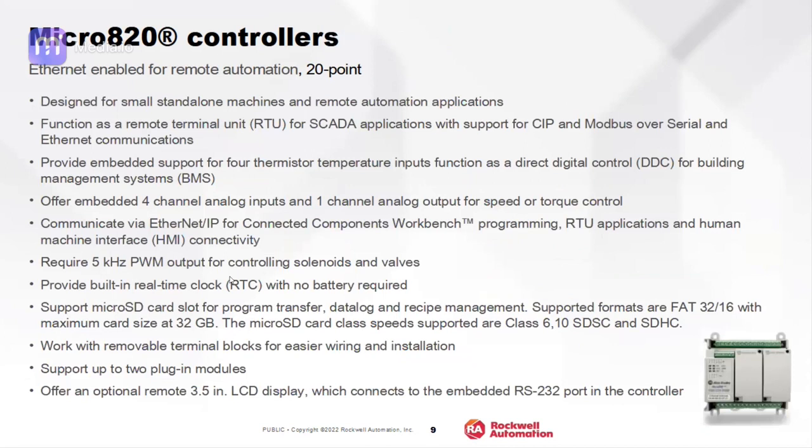The 820 is majorly designed for standalone machine applications and remote automation applications, like a small pump house. If we want to control the pump operation, we can put in an 820. It supports RTU, remote terminal unit connections, with either Modbus communication or Ethernet communication. Yes, it supports both.